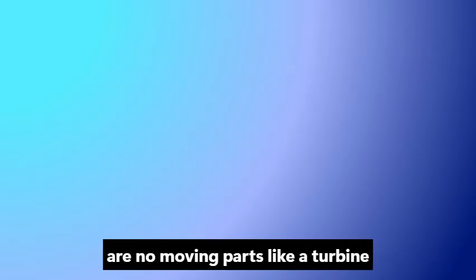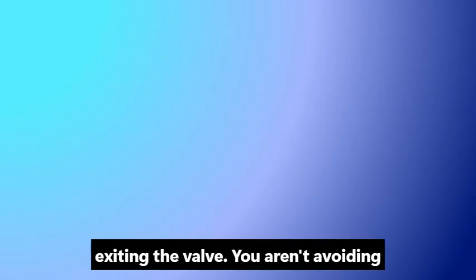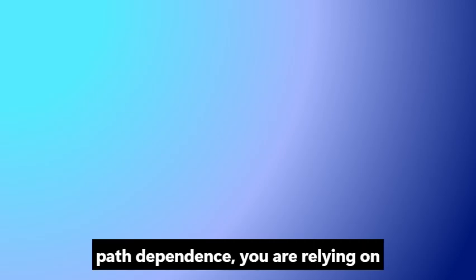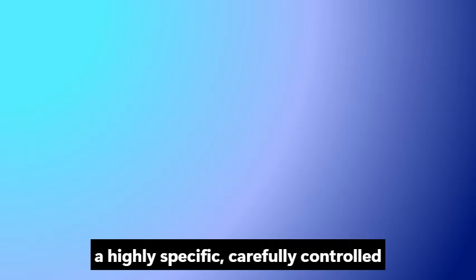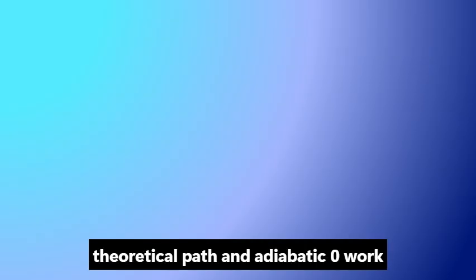And because there are no moving parts like a turbine blade, zero work is done. Right. Therefore, the theory dictates that the enthalpy of the steam entering the valve perfectly equals the enthalpy of the steam exiting the valve. You aren't avoiding path dependence. You are relying on a highly specific, carefully controlled theoretical path, an adiabatic zero-work expansion, to reveal the original mainline's enthalpy. The theory is doing the heavy lifting here. The hardware is just the messenger.